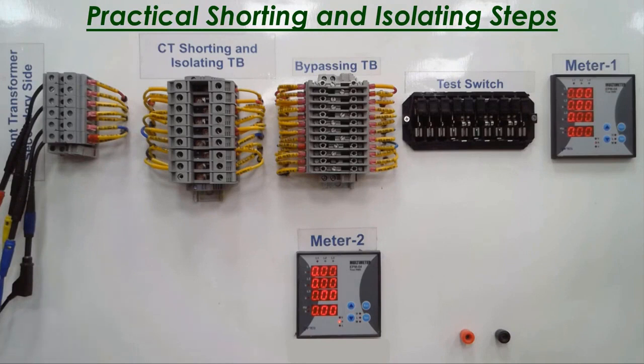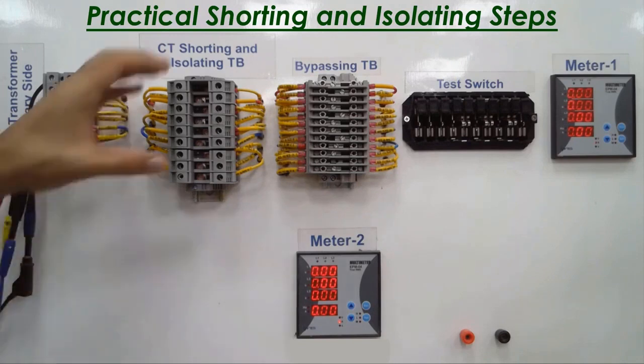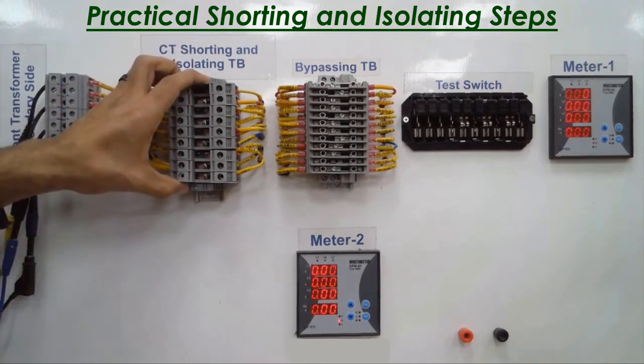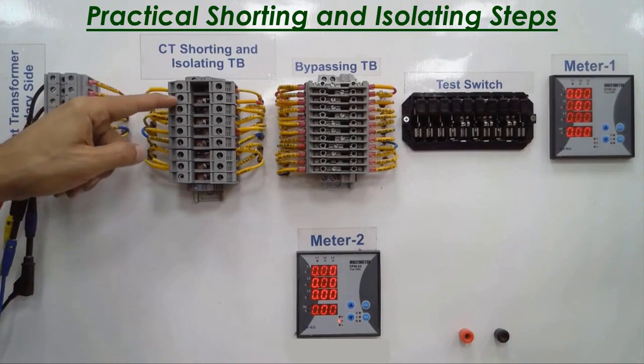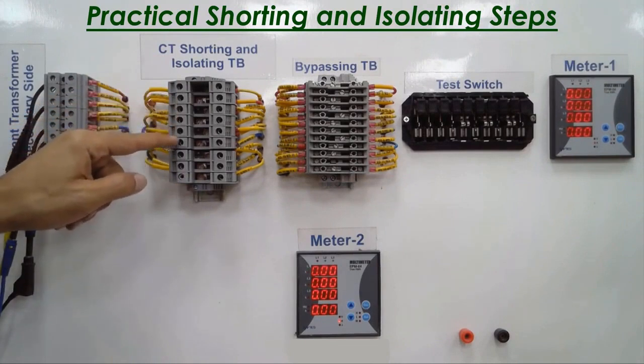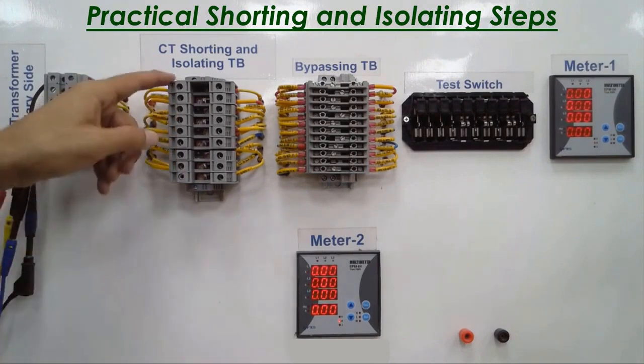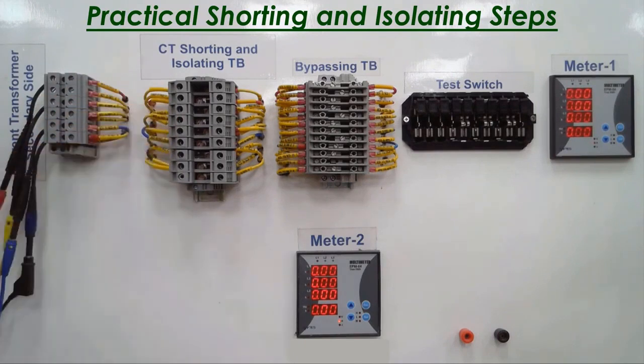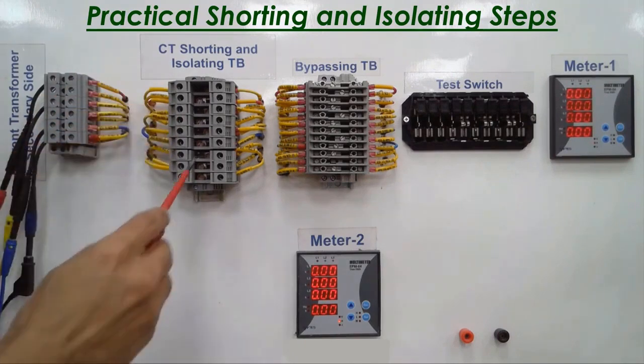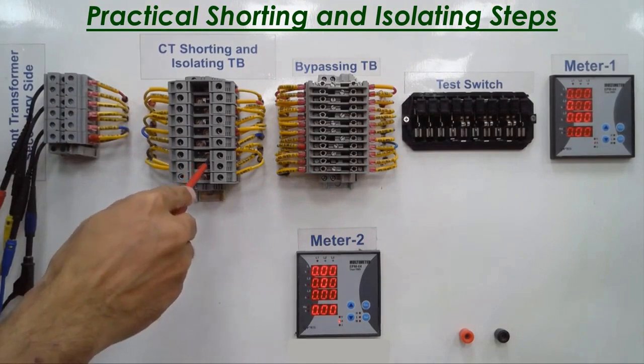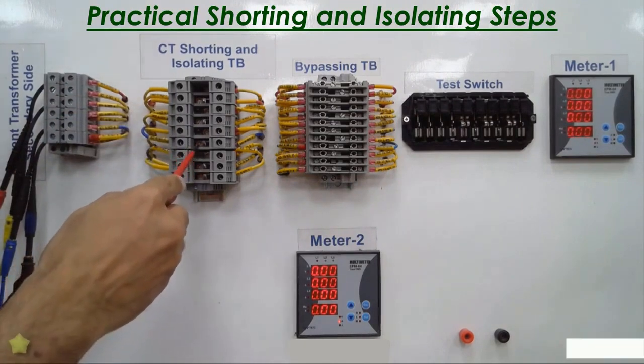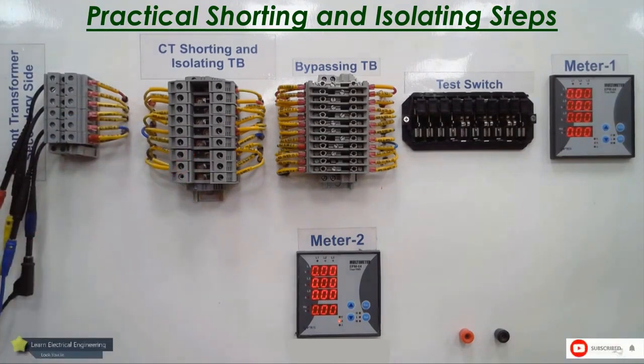But before I inject into my circuit, I need to ensure that my circuit is in the normal position. So of course, here I have the shorting and isolating type, and its normal position is that terminals 2, 4, 6, and 8 are closed, and terminals 1, 3, 5, and 7 are open. So the idea of open is that you will find the link on your right side, and for closed, you will find the link on your left side. As for the finger type test switch, you will find all the fingers closed.